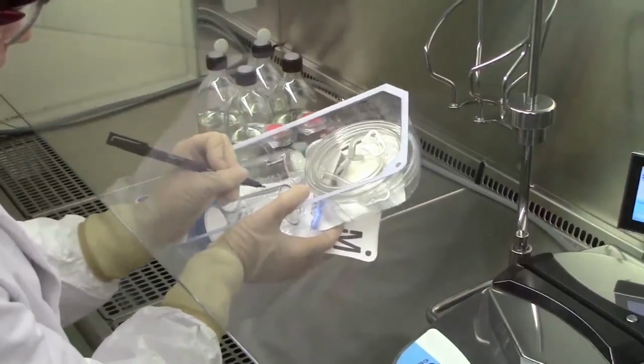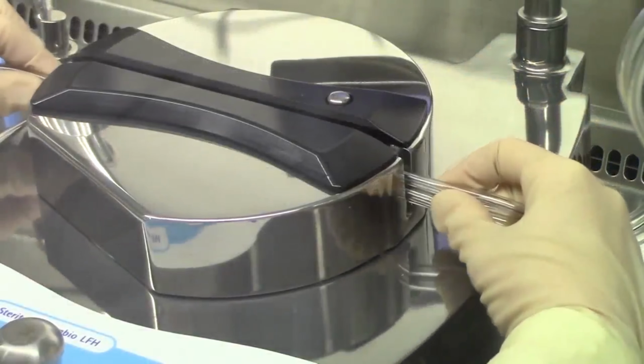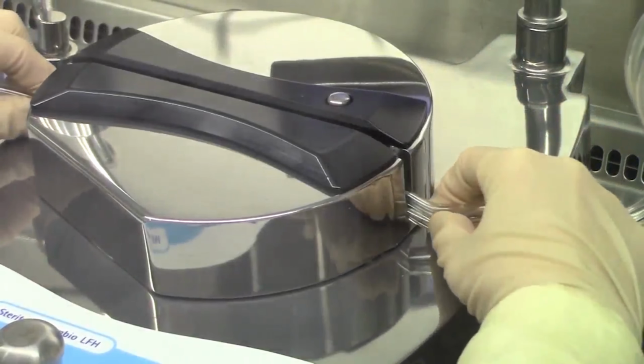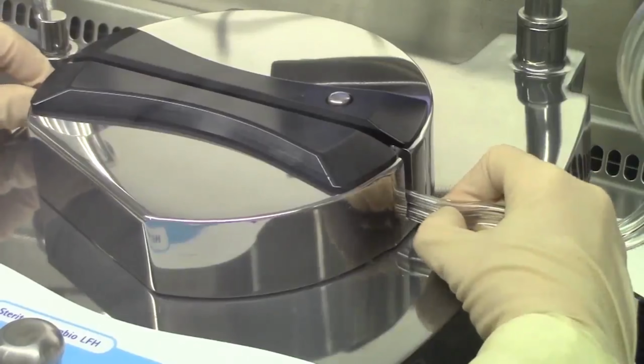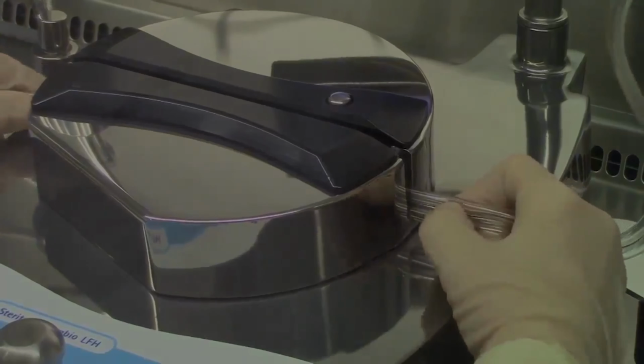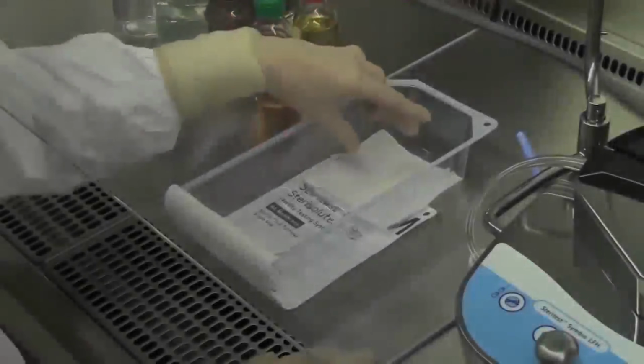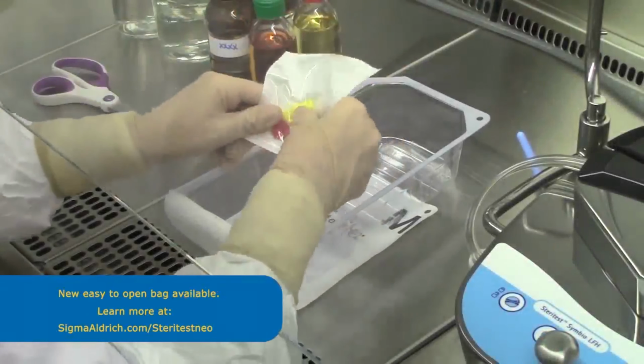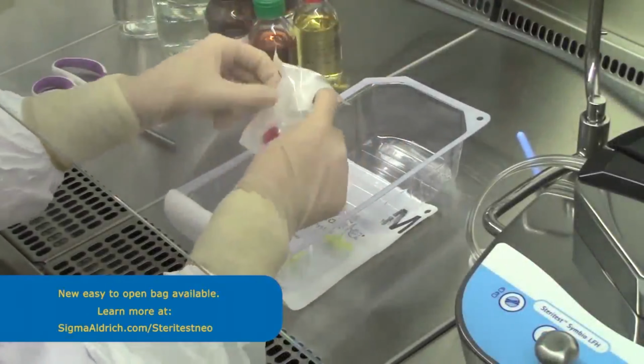Take the tubing straight, push it down in the cover. Make sure the tubing is positioned properly on either side of the tubing guides in the pump head. Slide the tubing from left to right and right to left to ensure that it is correctly positioned. Make sure that the tubing connected to the canister is not under tension. If necessary, slide the tubing to the right in the pump head. Close the pump head by pressing the button. Empty the plugs from the accessory bag into the blister.